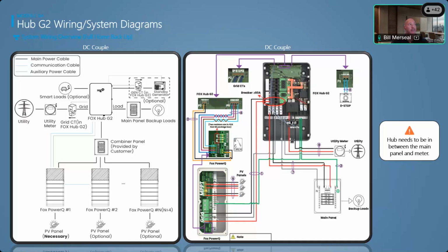The color is going to match. So blue, red, brown, and light blue will match when you put it into the inverter. The COM out on the hub goes to the COM in on the inverter, so you color code it. One thing on our system is that every wire is labeled on the board itself.